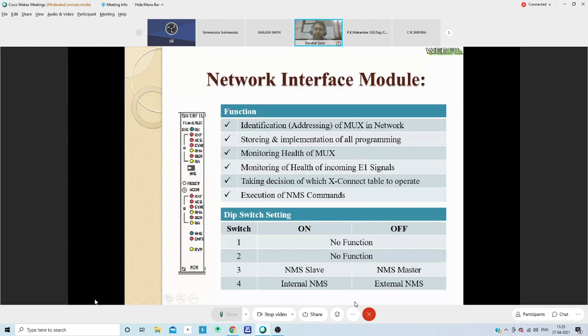There are some DIP switches in the NIM card. Other than the address, you also need to make sure your NIM card DIP switches are set properly. Of the four DIP switches, the first and second have no function, and the third and fourth you have to keep on under all circumstances.